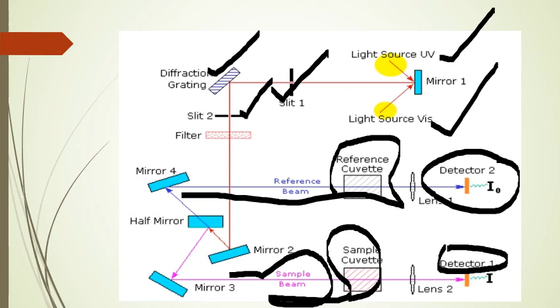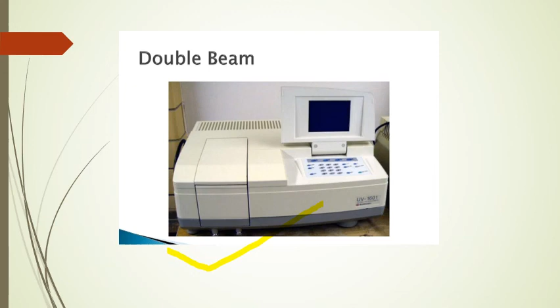So this is how the parts are attached in the UV visible spectroscopy instrument, and we have the analysis of the compound. The reference cuvette and sample cuvette are made of the same material, quartz or fused silica. So this is the double beam instrument in the lab, where we have seen in the diagram how it works. The double beam spectrophotometer is very useful compared to the single beam, as the analysis can be done simultaneously in less time.